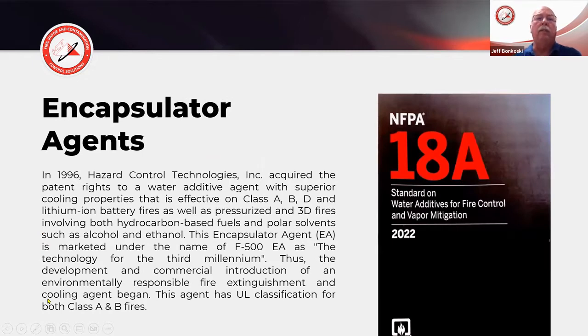So this has been around since the standard in 1996. Like I said, the first water additive was purchased by HCT. It was reformulated, and we now have F500, which we've learned is very effective on all classes of fires - Class A, B, D. In the 2022 edition standard, if we go into 18A and the annex materials section 4.3, we'll see there's even information showing that third-party agencies have tested it on lithium-ion batteries, with very promising results.